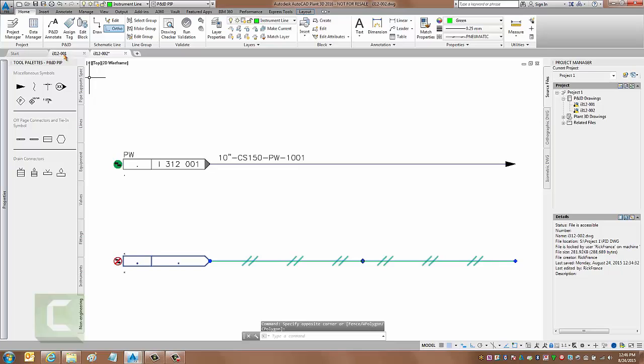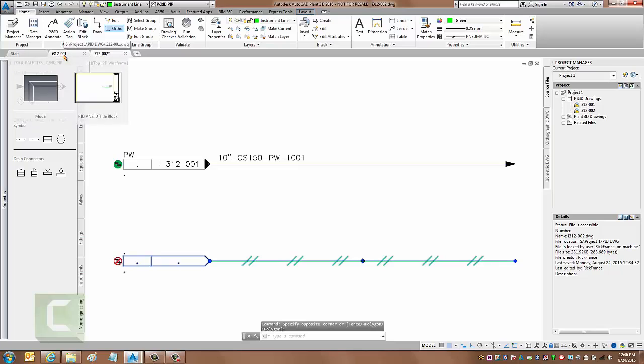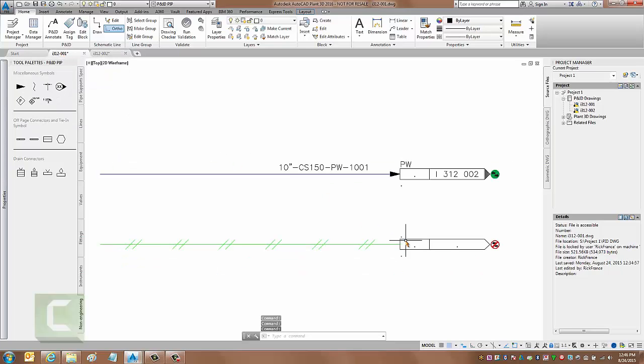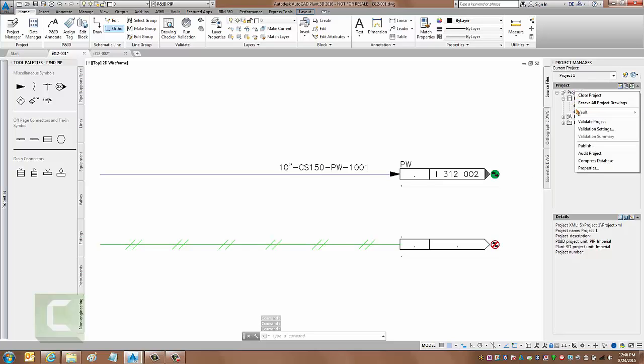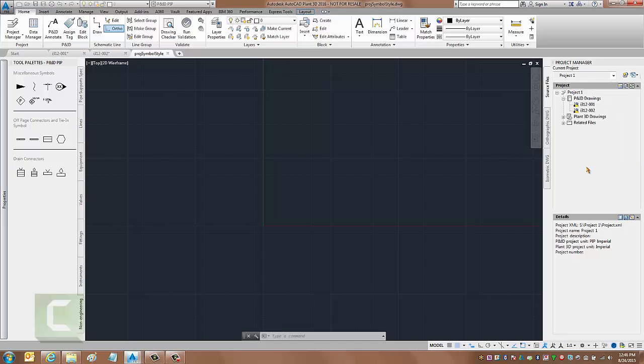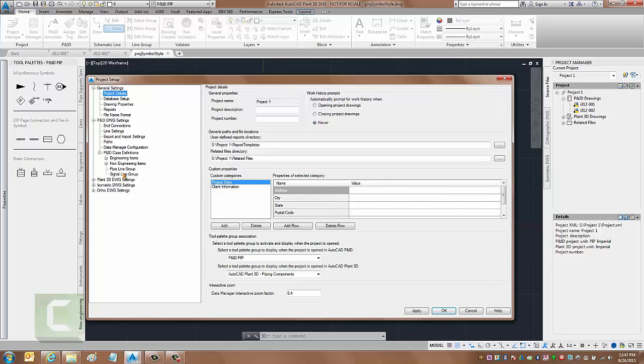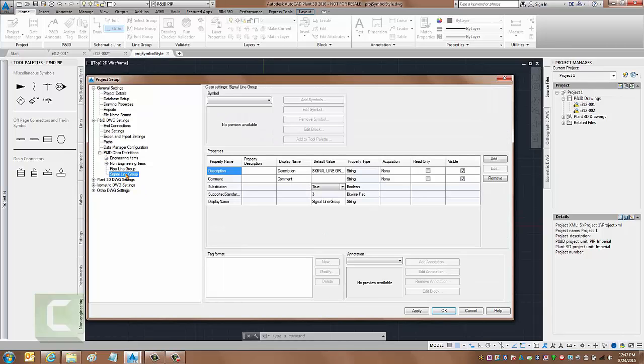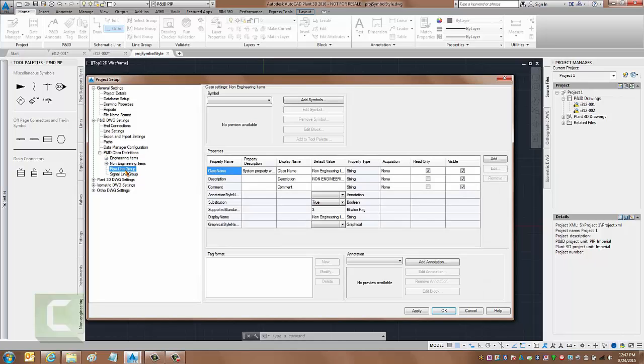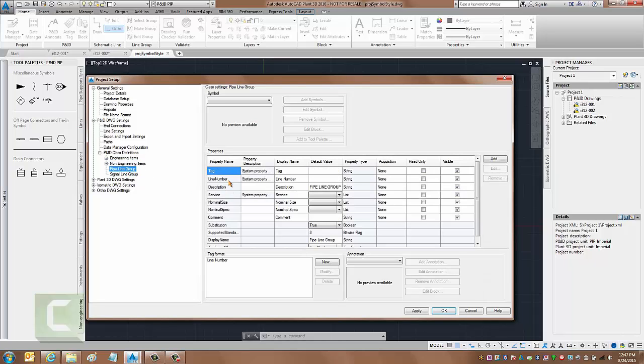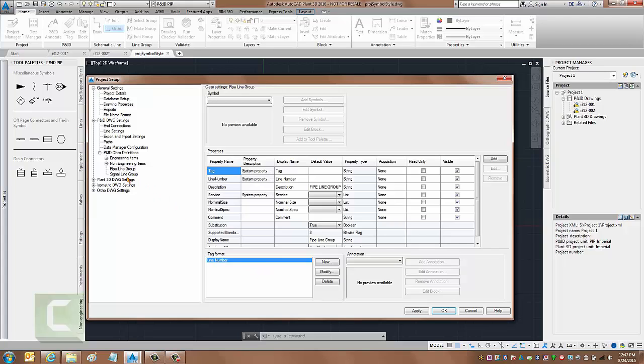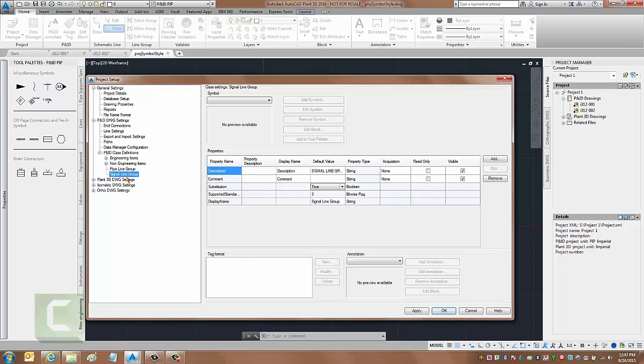So what we need to do is a couple things in our setup. I'm going back here to the first page, and I'm going to go to my project properties and get to my PSS file. Under P&ID settings, class definitions, here's my pipeline and signal line group. You'll notice here on the pipeline group, there is a line number being defined in the tag format. Here on the signal line group, though, there is not a line number. So there's not a line number for me to assign to it in order for it to see it to go from page to page. So that's the first of the three steps that we need to do, we need to add this line number.